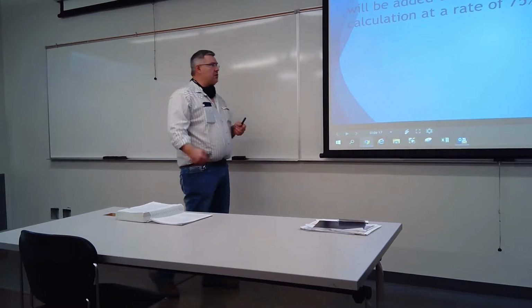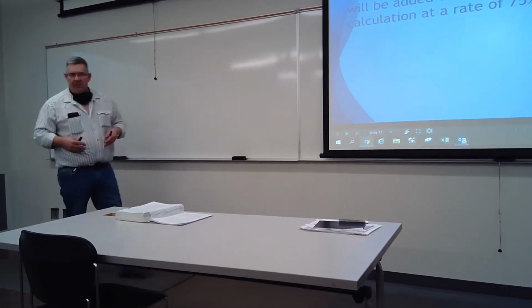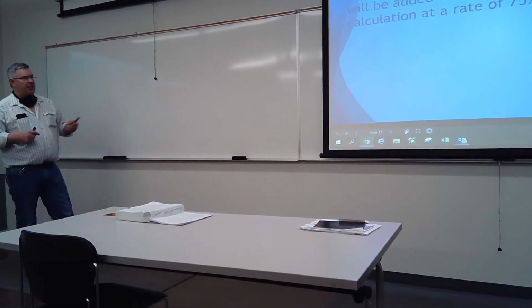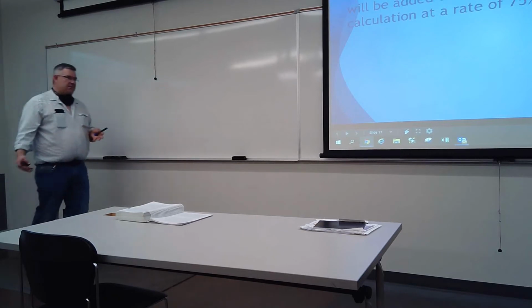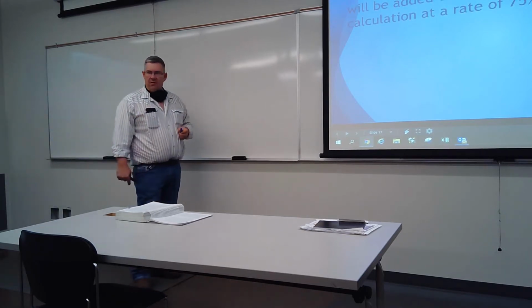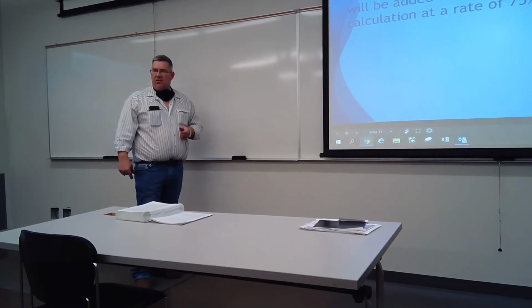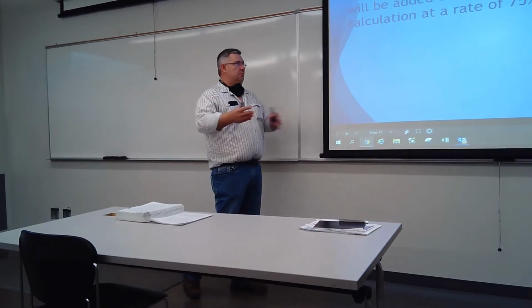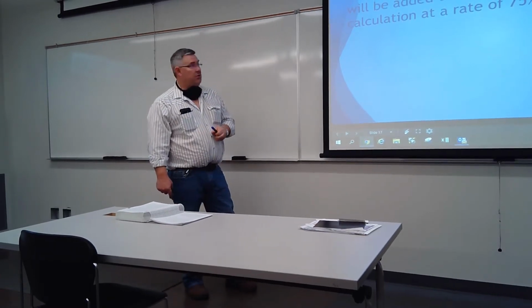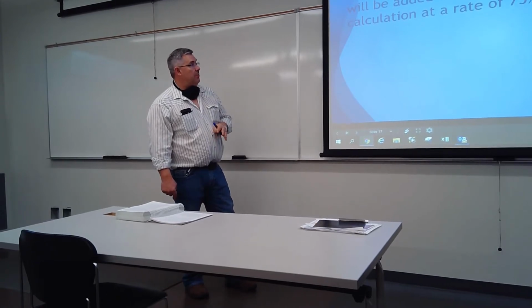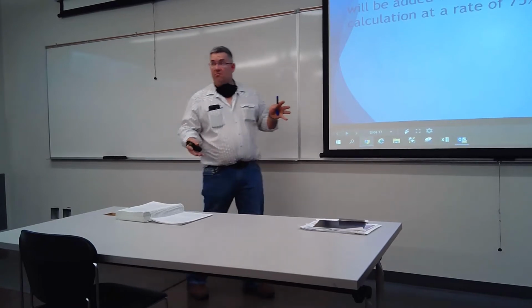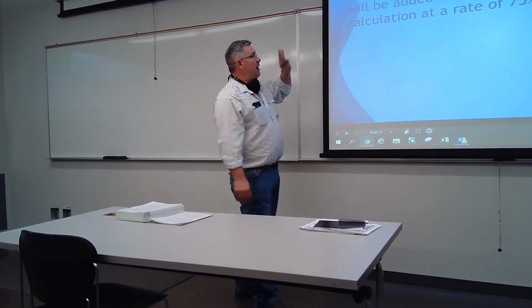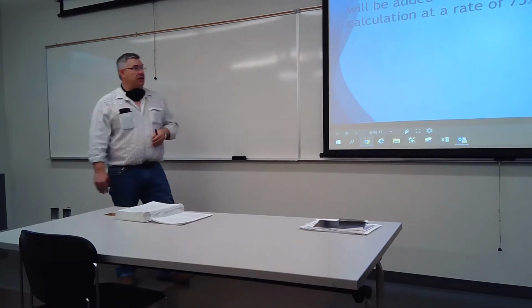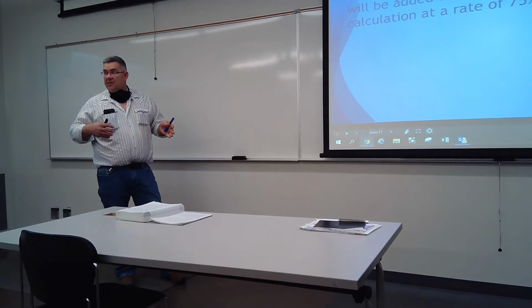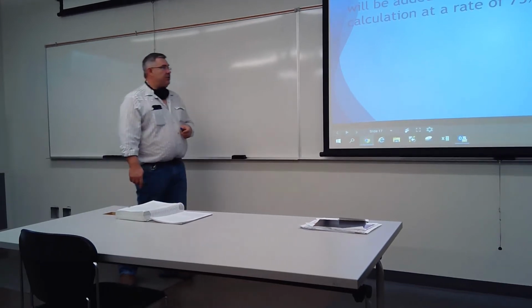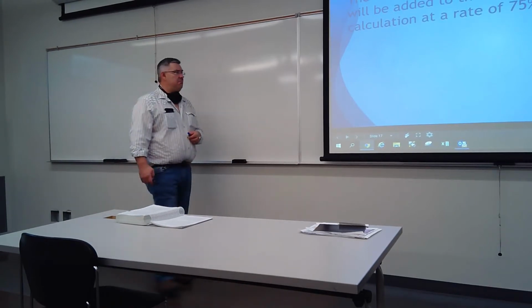Now, all those loads that are outside of the dwelling units, when we calculate them all up, we add them at a rate of 75% to our main service, and that's because, again, not everything's used at the same time, but we have to allow quite a bit of that load. So what we do for an apartment building is figure out your demand based on the dwelling units, then determine everything that's located outside of the dwelling units, everything that's common, and add that to your main service at 75%, and that's how you determine your full apartment main service capacity.